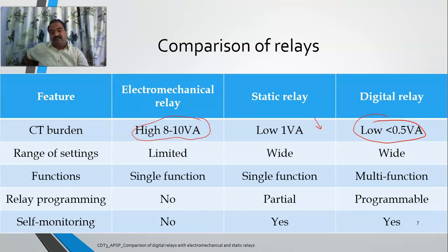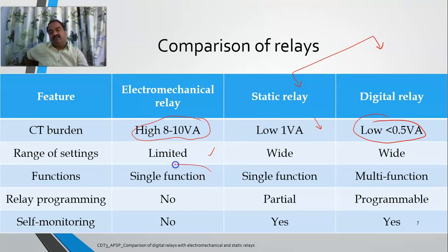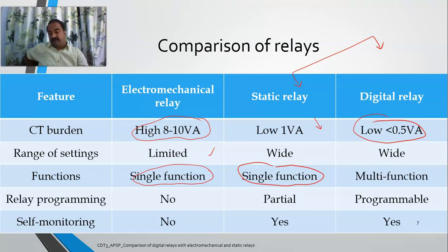Regarding the range of settings: digital relays offer a very wide range of settings, whereas electromechanical relays have a very limited range of settings and limited functions — mostly single function. Static relays are also mostly single function. Digital relays, which use microprocessors with dedicated memory and advanced microprocessors, offer very high multifunctionality.